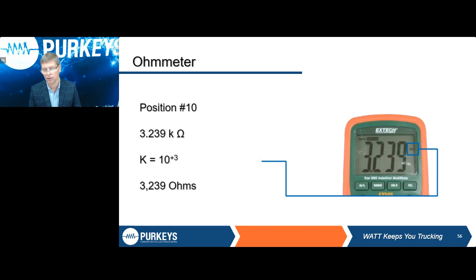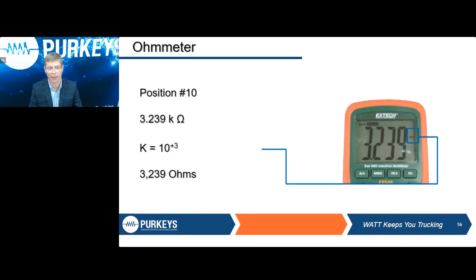The Extech and Flukes, most of them will go up to 40 meg or 40 million ohms. I've seen techs out in the field using meters that only go to 4,000 ohms. So even just that sensor that has to be at least 6K, on a meter that only goes to 4,000, if he tried to check it, it would read OL, saying it's above 4,000. First reaction would be, oh, it's open, it's infinite, it's well above. Well, what if it actually had a resistance of 4,500 ohms? It's above what his meter could read, but it's not high enough to meet that spec, and you would wind up leaving a defective sensor in that situation.